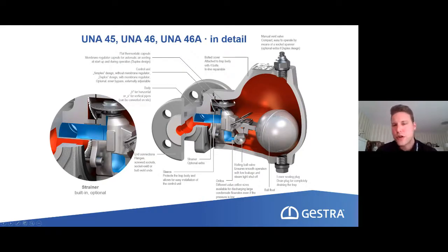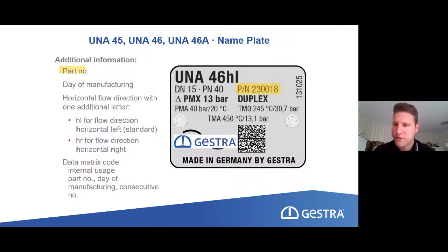So as soon as we have air here in the body of the steam trap, the temperature will drop because of the low heat transfer of air. This membrane detects this temperature drop, and if the temperature is too low, it will open, and then the air will be discharged to the condensate line, and we don't have it in the process anymore. And if we have reached the steam temperature again, this one will close, and then, let's say, the control unit will go back into its common or usual operation. Very simple design, which works fine. Okay, we can get a lot of information by taking a look at the nameplate.